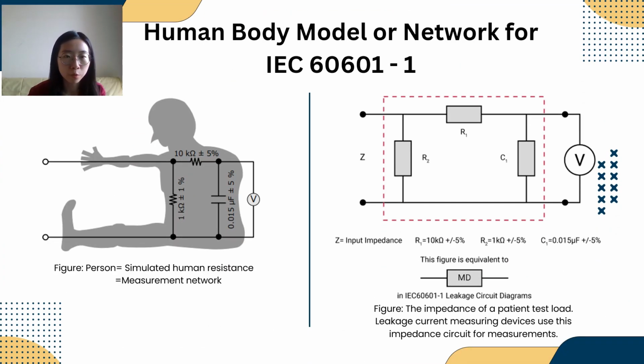So now I would like to present the theoretical calculation. These two figures show the human body model or network for IEC 60601-1. Here is the circuit showing a person equivalent to simulated human resistance and the equivalent measurement network. Here is the circuit showing the Z input impedance. R1 equals 10 kilo ohm, R2 is 1 kilo ohm, and C1 is 0.015 microfarad. All of these have plus or minus 5% error.